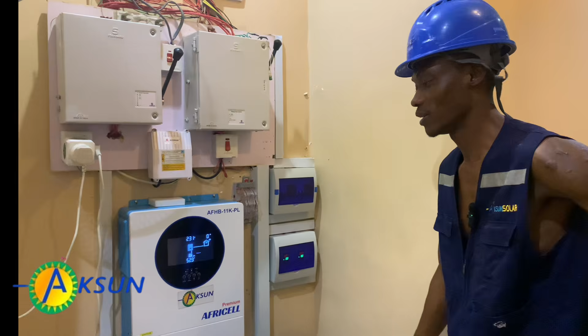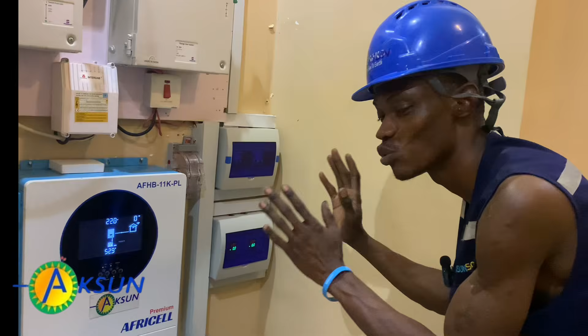I've connected my communication cable from the inverter to the battery without even going to the settings to select what type of battery I'm using. Automatically it has detected that I'm using a lithium battery and it's already communicating. Bring the camera closer, let's see what we have here. Now you can see it shows lithium, meaning my battery has been detected as a lithium battery, 52.9 volts, 30%. Now let's check from the battery: 52.9 volts, can you see? Let's check the percentage also, 33%. So this already signifies that our battery and our inverter are communicating well, quite alright.